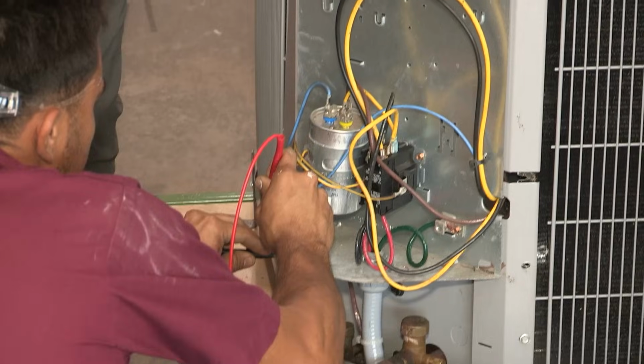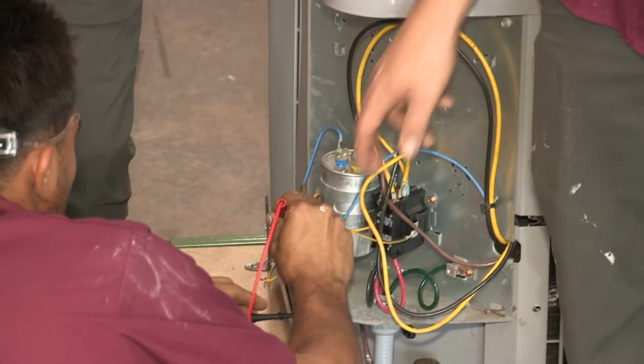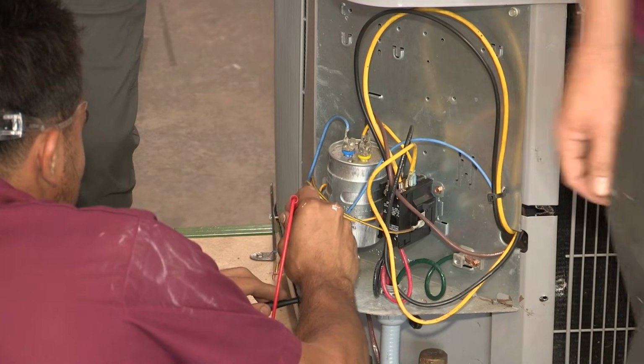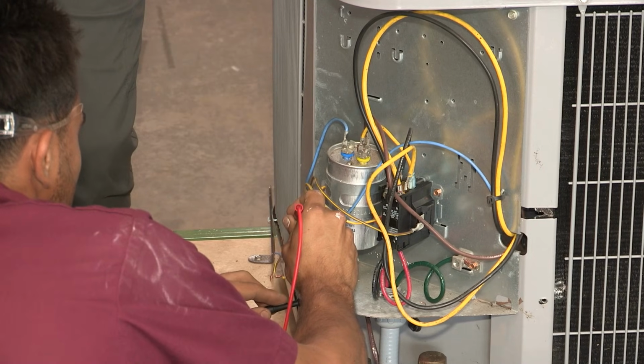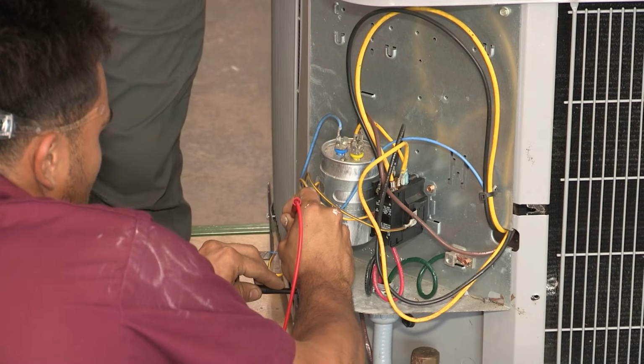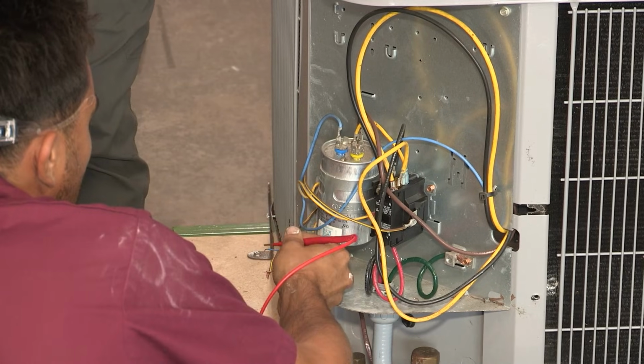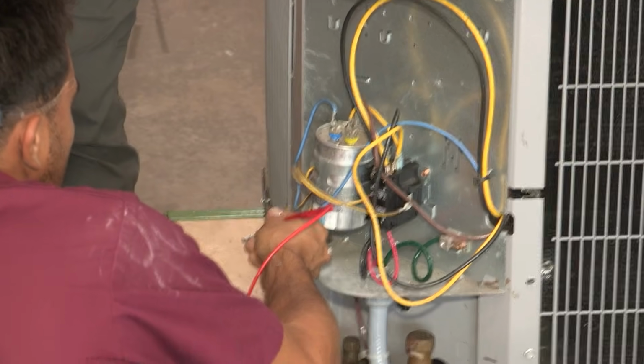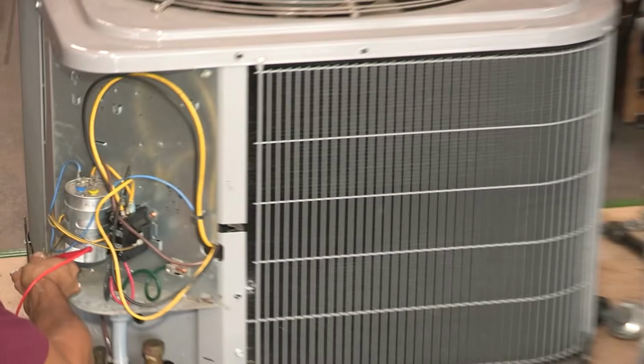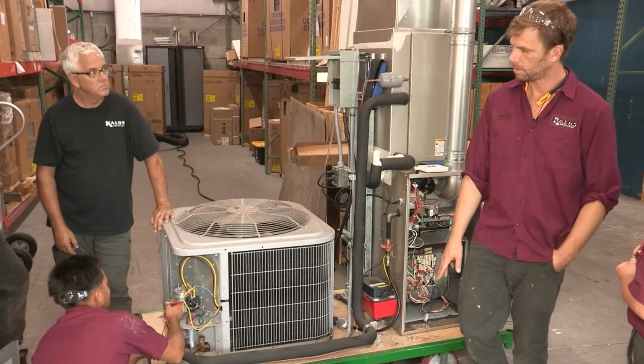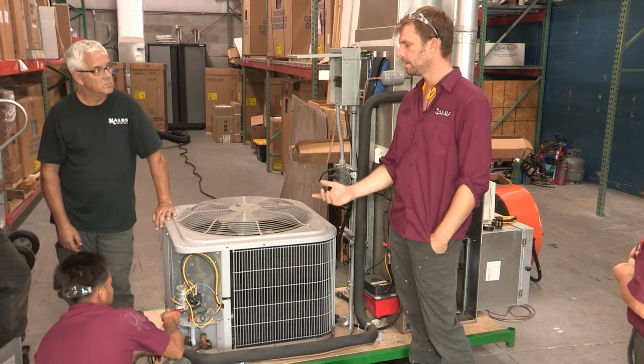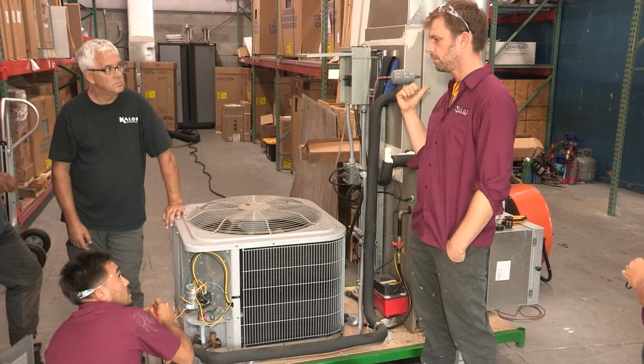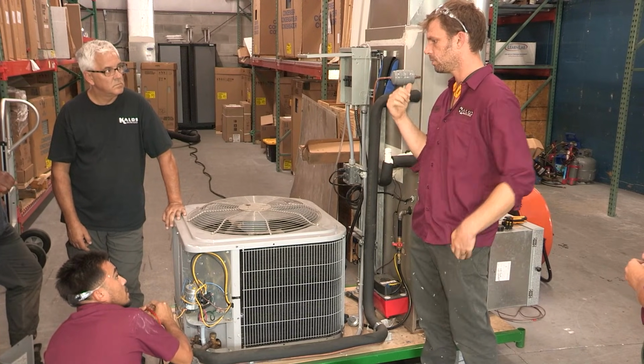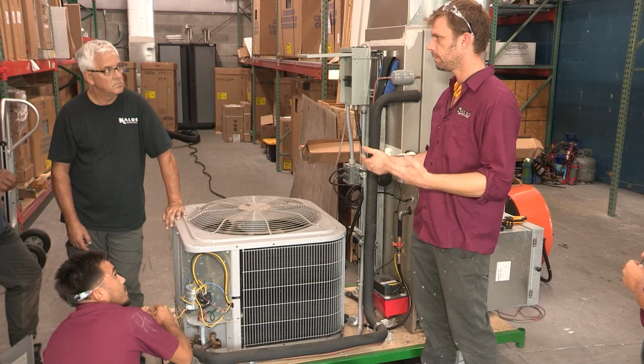Now what yellow are you checking? You're checking the yellow going straight to here. We're supposed to be checking the low voltage wire. Okay, any path there? So according to the meter, we don't have a path on our yellow thermostat wire between here and connected all the way back to this unit. Okay, and remember what we said about common? Common is grounded at the transformer. So there should be a path, which is why we removed it, so we wouldn't get confused by that.